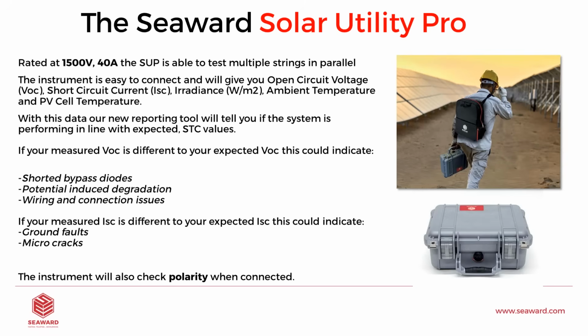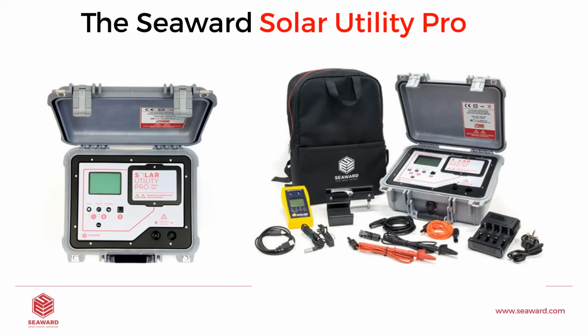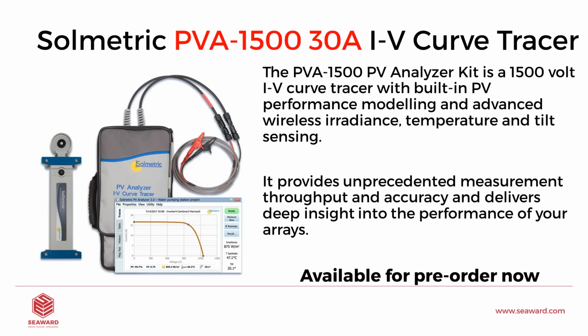So before you begin testing, please ensure you have the correct equipment for what you need and don't take something to site which doesn't have a high enough rating. This is the unit itself, and you can also see what is in the kit. We have the irradiance meter, the temperature probe. We give you cables to be able to connect in a combiner box or at the end of a string. Also, we get a nice carry bag. It uses rechargeable lithium-ion batteries, and this is all included for $3,000 plus shipping, and it's available here from our office in Tampa and internationally.